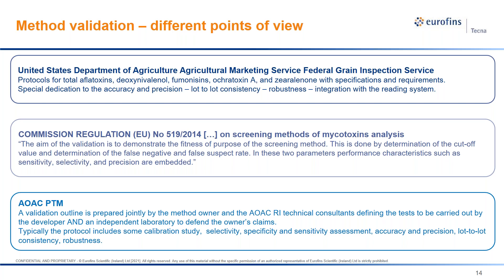The third approach is from the AOAC Research Institute, which also provides third-party approvals to analytical methods. The AOAC validation protocol is not strictly standardized like the FGIS but reflects specifically the claims of the applicant. It usually includes characterization and discussion of several aspects: typically calibration assessment, selectivity, sensitivity, specificity, accuracy, precision, consistency and ruggedness. Most experiments are in the hands of the applicant, and there will be a sort of confirmation demanded to an external independent entity.